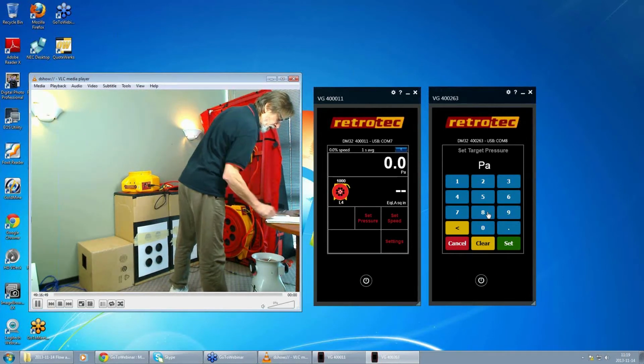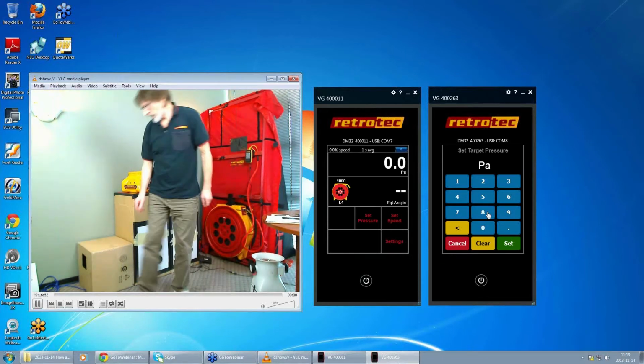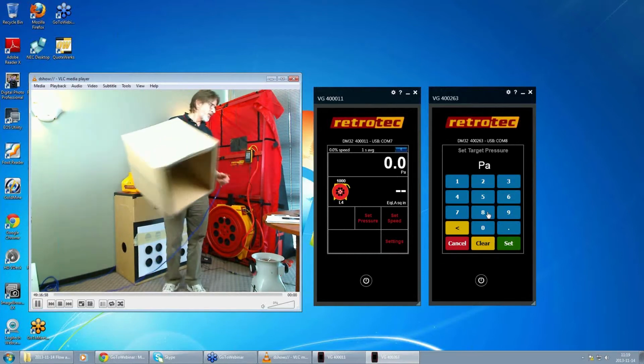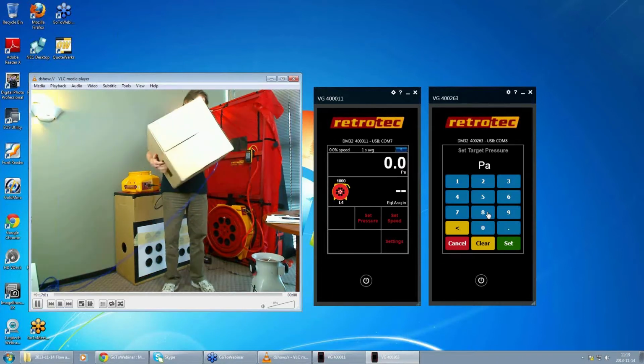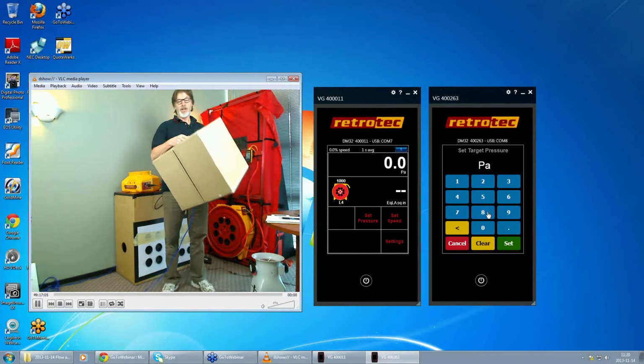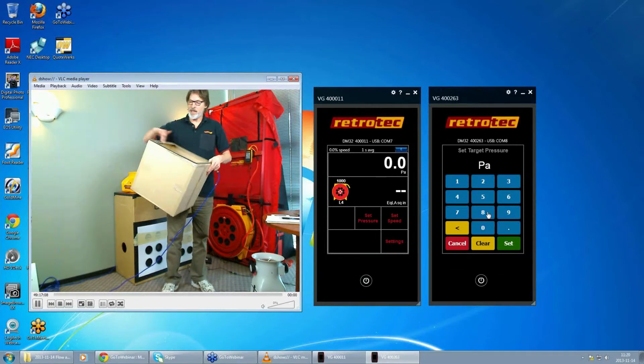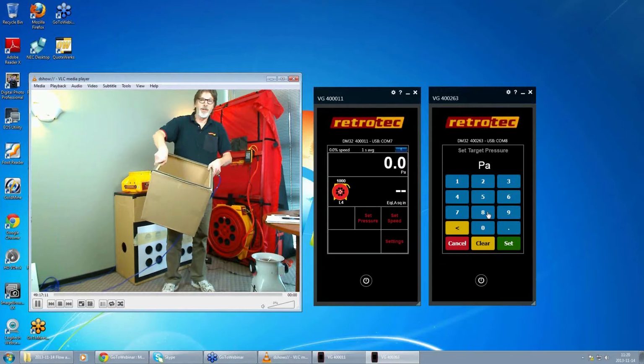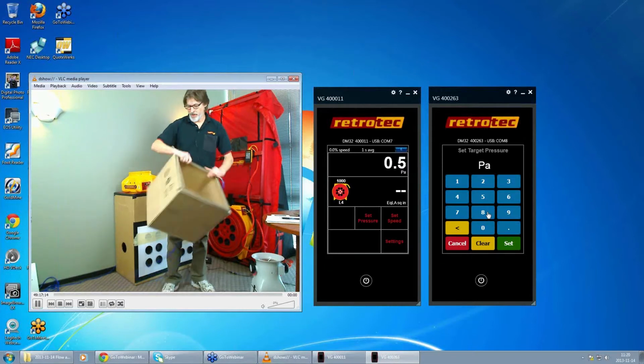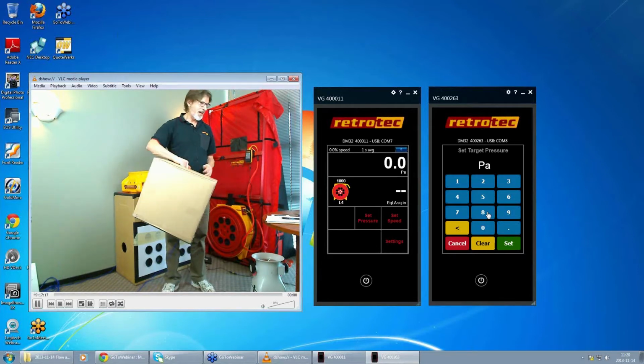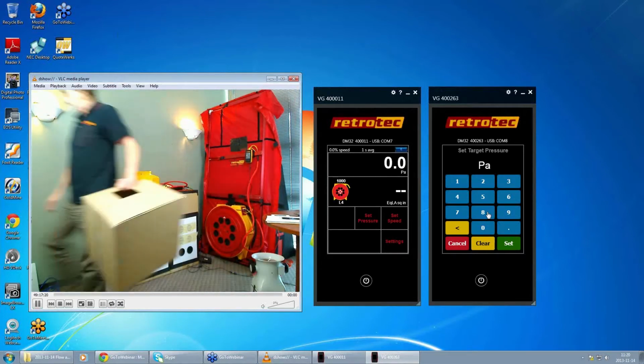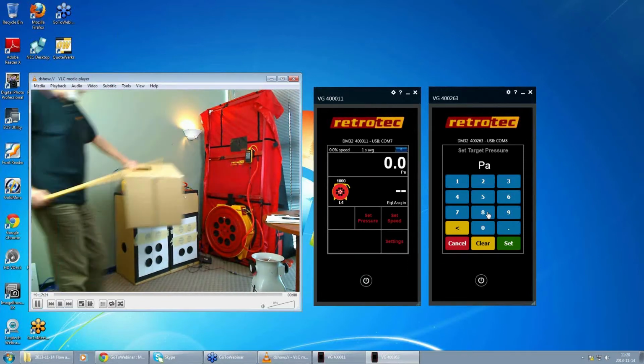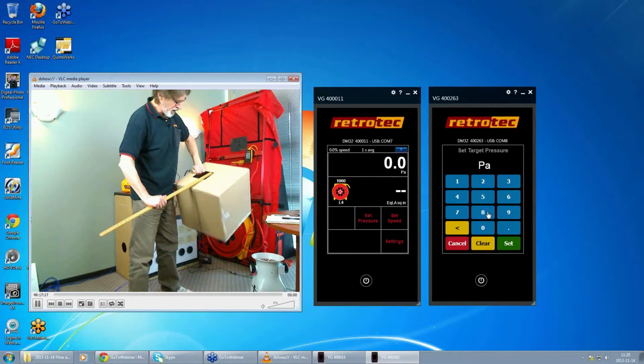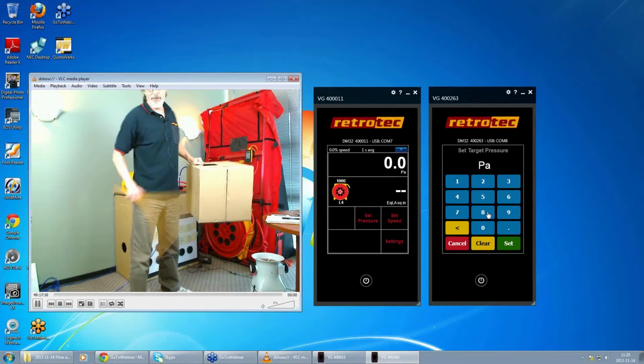Okay, the next thing we're going to do is take a look at a very fancy device, or unfancy, I should say. This is an exhaust fan box or a calibration check box or anything you want to call it, I suppose. It's just a simple box. I've got the end cut out, and I've cut it just short of the edge, so I've got a little bit of a flange here. Put a piece of weather stripping around it, and I've cut a hole in the end, which is exactly 5 by 5 inches. You can see it's kind of a rough hole. I just cut it out a few minutes ago.